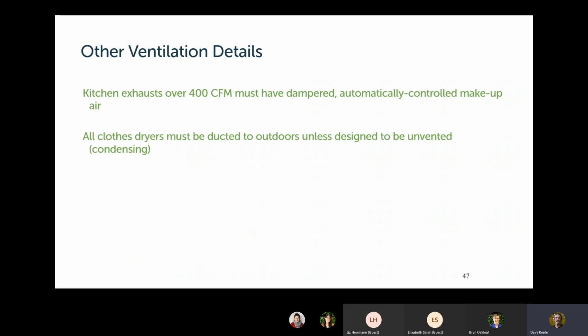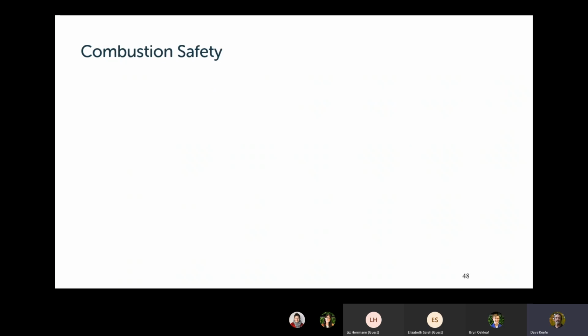All clothes dryers have to be ducted to the outdoors. There is an exception for condensing clothes dryers. You may know that you can buy a condensing clothes dryer now that is not designed to exhaust at all, and condenses the water out of the clothes and sends it down a house drain rather than pushing it out through the outside air. That's it on the ventilation stuff.